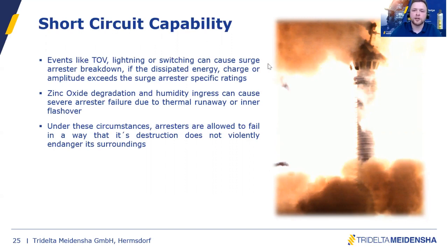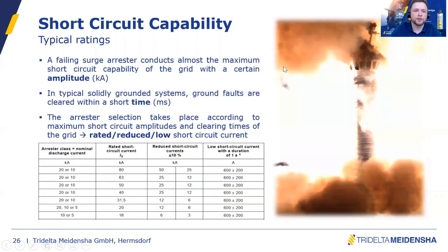And this is an interesting thing. I want to talk a little bit more about this. You can select the surge arrestor according to its short circuit capability. Important criteria are amplitude and time of the short circuit. Mainly this has something to do with the time until the fault is cleared in the grid. So we are seeing an amplitude depending on the capability of the grid, and a time depending on the time when the fault is cleared in the grid. And this always leads to a combination of current amplitude and time for this short circuit current. And the standard defines a rated short circuit current, which will always be the selection value. And there is a reduced and a low short circuit value, which belongs to a specific rated short circuit.